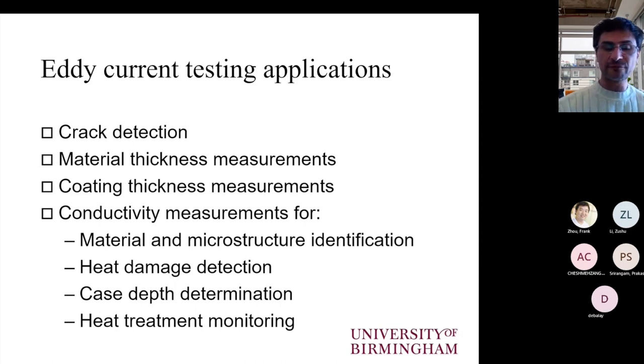And one way of doing this inspection is by applying eddy current testing, because the degradation of the thermal barrier coating will result in some changes in the relative magnetic permeability, to which eddy current testing will be extremely sensitive. So if we are picking up permeability-related variations, that means that our thermal barrier coating is degrading, and that can be quantified actually. Of course, we can also take into account conductivity measurements for material and microstructure identification.